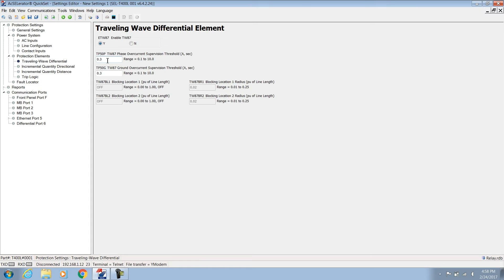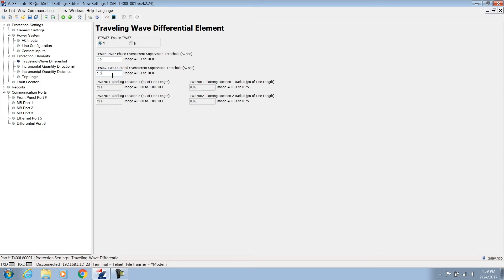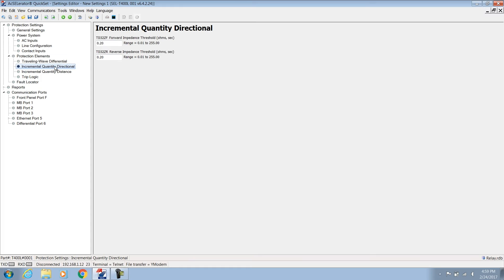Next, calculate the pickup values using simple formulas from the SEL-400L. Assume we calculate 2.6 amps for phase elements and 1.5 amps for the ground elements. Remember the effective CT base in this case is a thousand to five, so the 1.5 amp secondary means 300 amps primary.